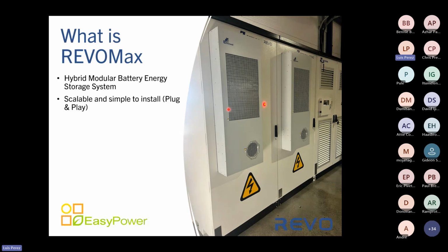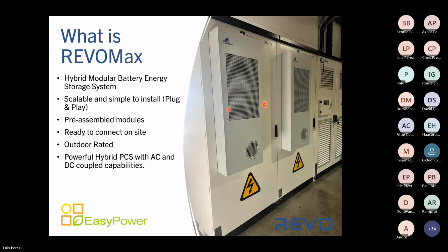Every one of those modules you see in the photos is an individual module that can be taken to site and interconnected. The modules are pre-assembled and pre-tested, so there is very little field work required to get the equipment to commission. The equipment is ready to connect on site, and we also provide customers with guidance on commissioning. They are outdoor rated, air conditioned, and sealed.